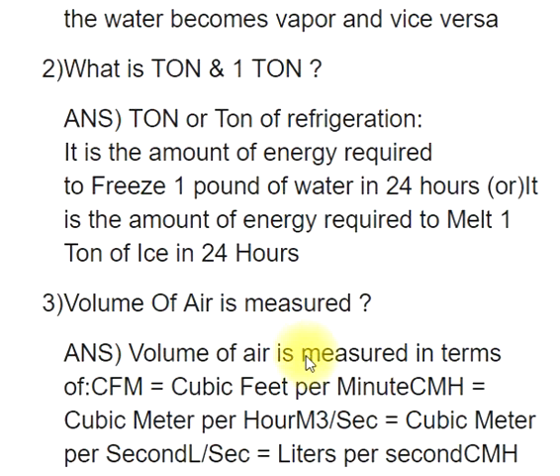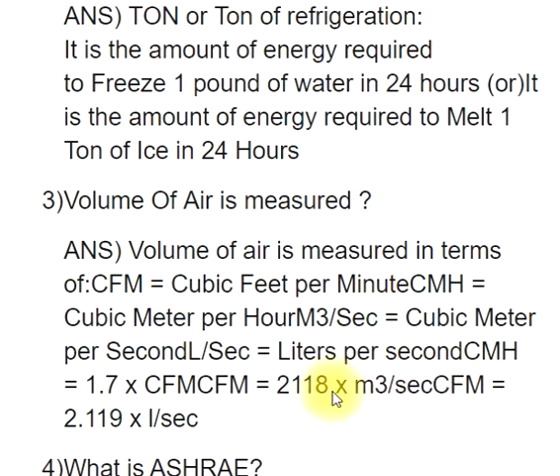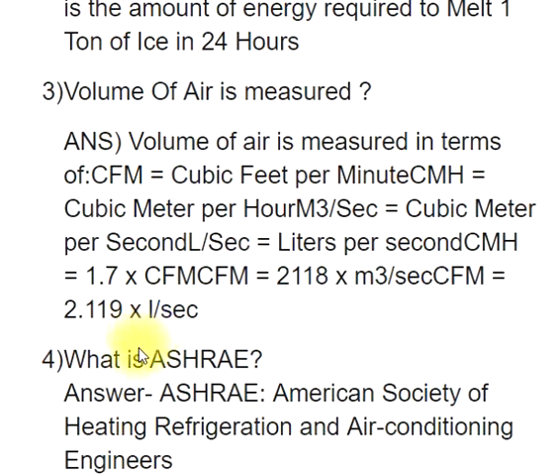Q3: Volume of air is measured. ANS: Volume of air is measured in terms of CFM (cubic feet per minute), CMH (cubic meter per hour), M3/s (cubic meter per second), L/s (liters per second). CMH equals 1.7 × CFM; CFM equals 2118 × M3/s; CFM equals 2.119 × L/s.